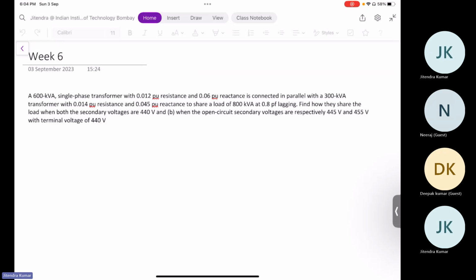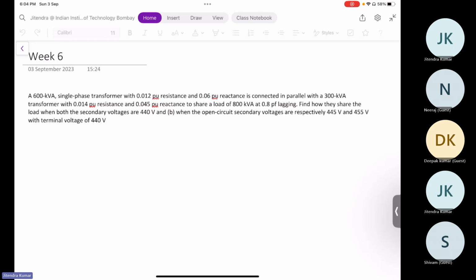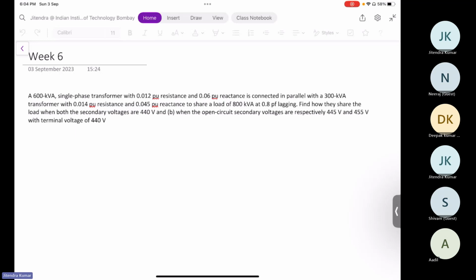Okay. One thing is that they must be connected properly as far as their polarities are concerned, so that the net voltage around the local loop is zero. You know that when two transformers are operating in parallel, they will have certain leakage impedances. So we don't want any circulating current to flow in the circuit, because the leakage impedances are fairly small, and in such a case, you will end up with very high circulating current. So we don't want that to happen.